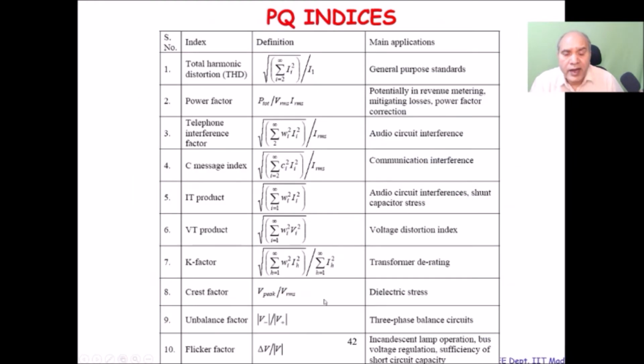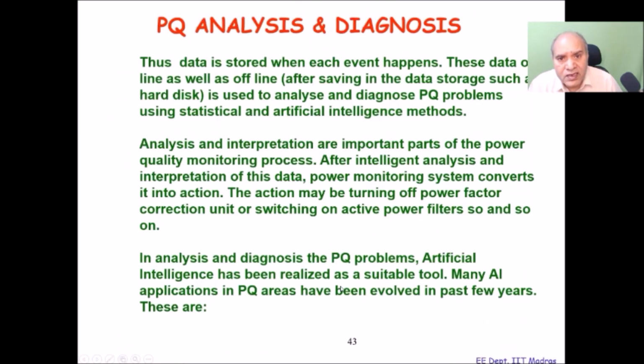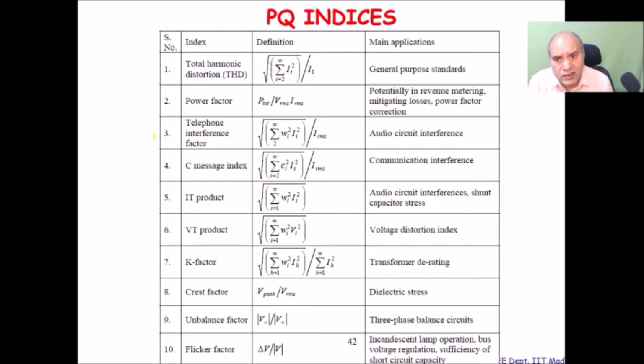And apart from that, there are other indices that can be looked into for measurement, like THD, as you know. Power factor is another parameter. Telephone interference factor is the square root of the summation of the weighted squared values of the current or voltage, divided by IRMS. Then the C message index is similar, except for a difference in the weighting of the current or voltage. The IT product is the square root of the sum of squares of WI times II, so this is like a weighted RMS value.